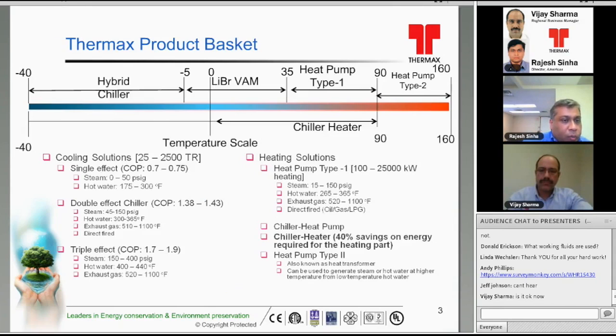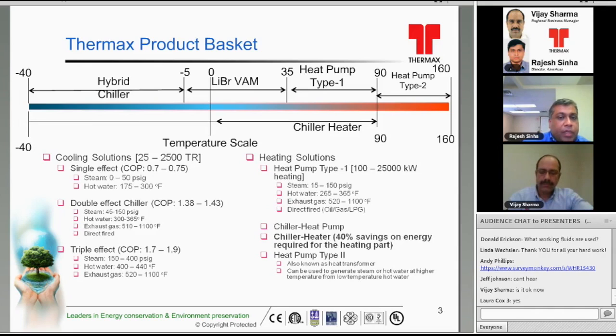which gives you the whole range of products which we have. So we go from minus 5 degrees Fahrenheit up until minus 40 with the hybrid chiller, and beyond minus 5 up until 35 degrees is the lithium bromide water cycle chiller, and beyond that is the heating cycle, which is the heat pump application, type 1 and type 2, which takes care of temperatures of 90 to 160 degrees Fahrenheit.